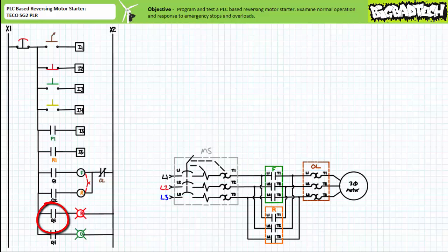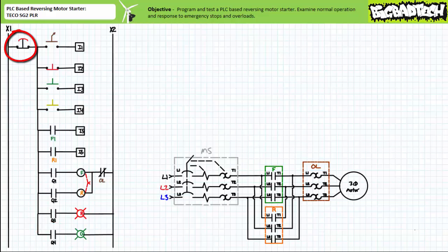Electromechanical relay output Q3 directs the operation of a red pilot lamp, and electromechanical relay output Q4 directs the operation of a green pilot lamp. Note the maintained contact normally closed e-stop also serves as a hardwired bottleneck through which all field output devices immediately downstream of it must negotiate to be energized. Wired in this fashion, the hardwired e-stop upstream of all field output devices effectively severs all outgoing communication from the PLC without any programmed instructions.